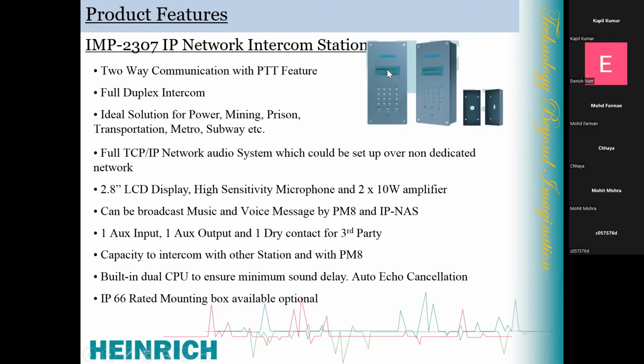This is an intercom device. If you can see, it has a keypad as well. There are two types of intercom devices. One is single button and one is multiple button. The single button intercom system is used where you want to have two-way communication with the control center only. You just push your single button, and the call will appear in the control center or the selected microphone.